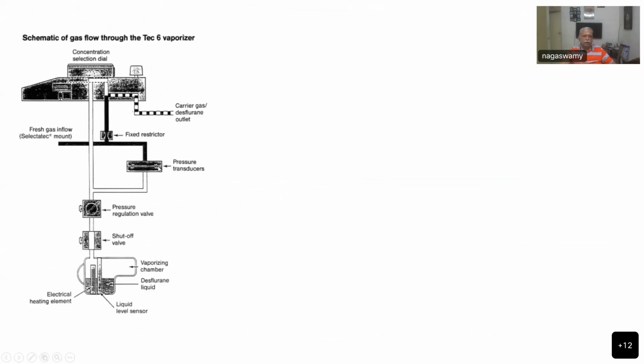You can see this is the pressure transducer here. There is the fresh gas. This dark tube is the fresh gas flow, and the sump containing the liquid is here, which is getting heated, and immediately at the outlet of the sump there is a shut-off valve. Then there is a pressure regulator valve, and this is going to get mixed with the fresh gas flow. So the fresh gas inlet is here, and there is a fixed resistor for that. This resistor is important because we can vary the fresh gas flow and still get the same concentration output.